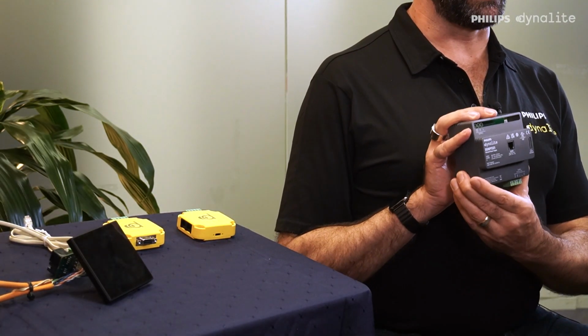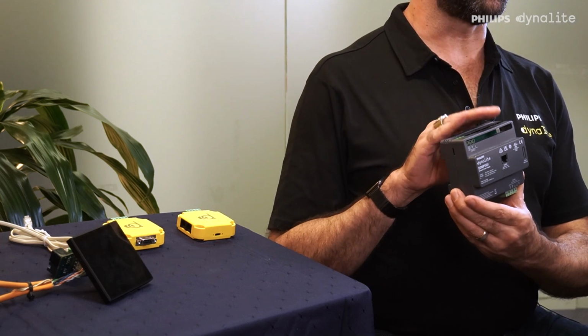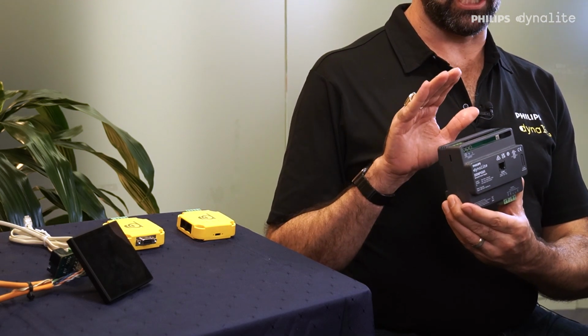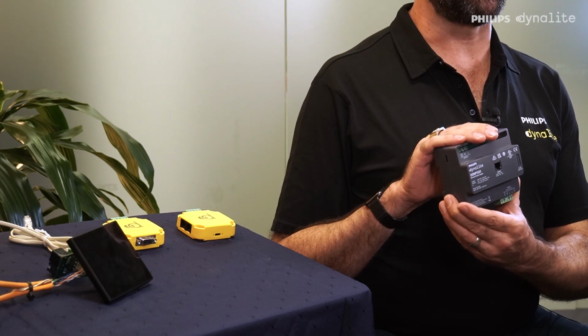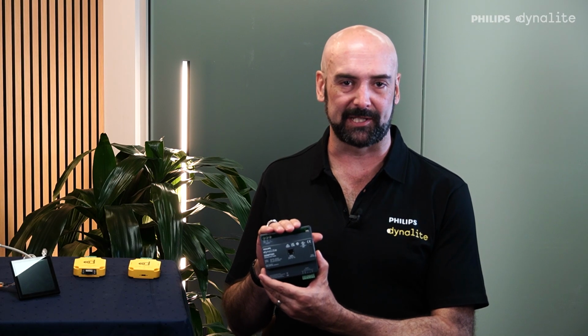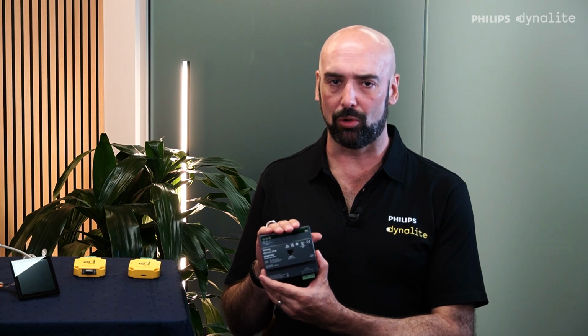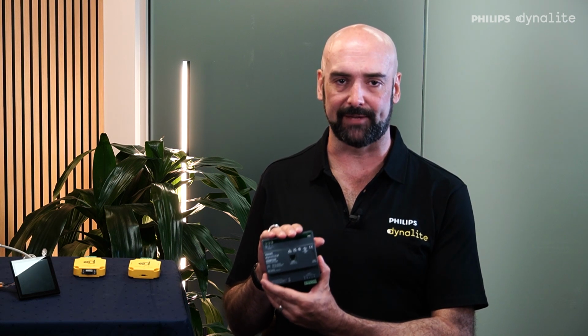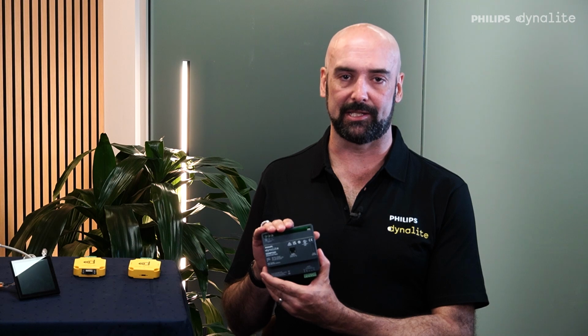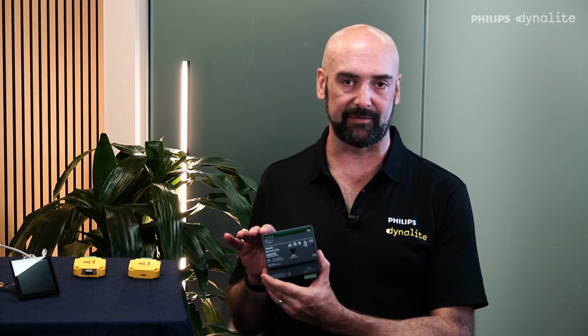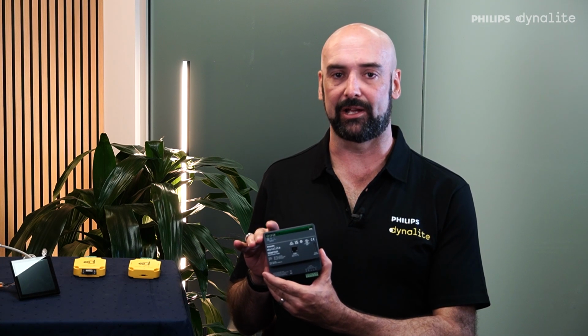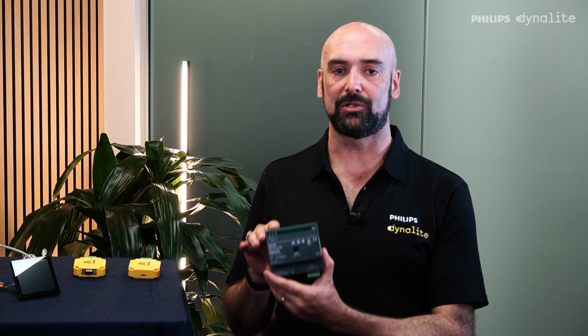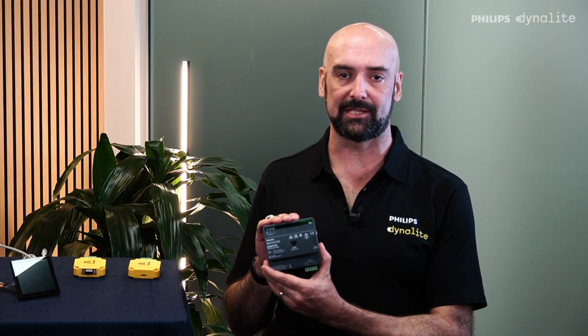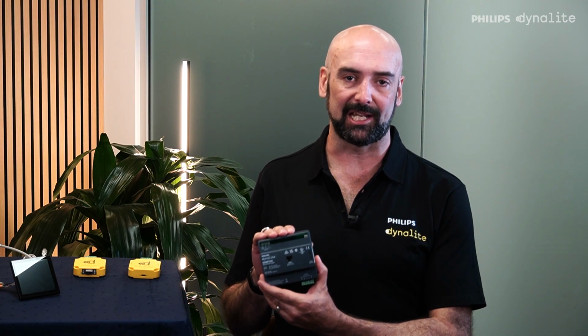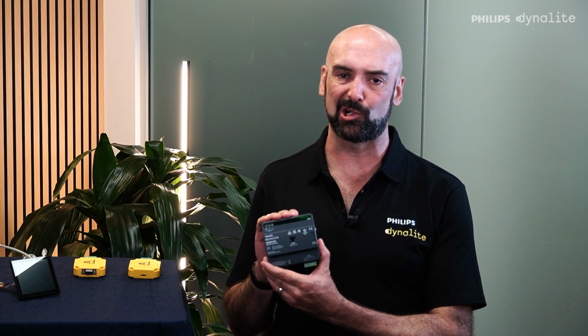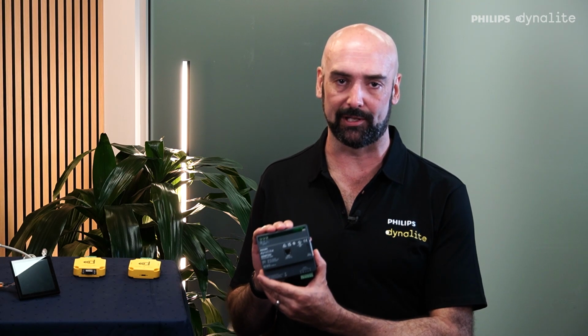Additionally, we're updating our network power supply, the DDNP1501. It's been a very popular network power supply for us, allowing us to meet project specifications requiring that all network devices are from the same manufacturer. This network power supply has had its voltage increased - it used to be 100 to 240, now it goes to 277, allowing for use within UL markets. It has received its UL certification, meaning it's been externally tested to meet incredibly high and stringent safety and quality standards.